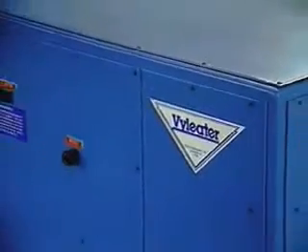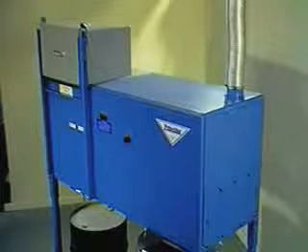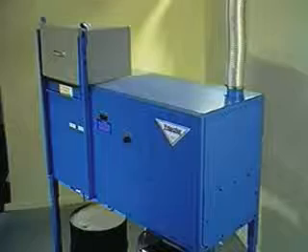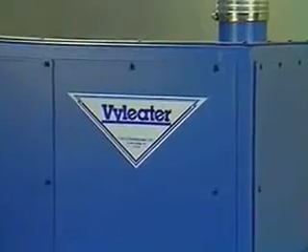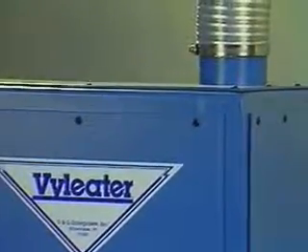Because of its compact size and quiet operation, the Vyleater is especially suitable for use in laboratories. Its narrow width permits it to pass through standard doorways. The machine is totally enclosed. Internal fumes are removed by a blower which has a capacity of approximately 250 cubic feet per minute. It discharges through a 4-inch vent which can be connected to the building's fume exhaust system.